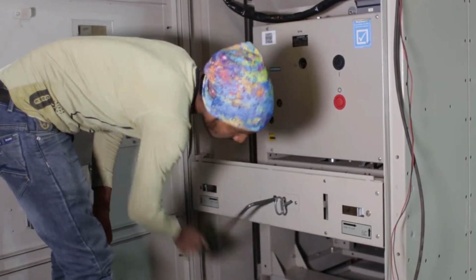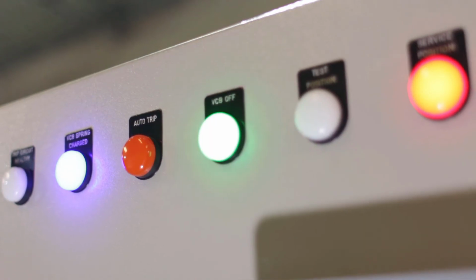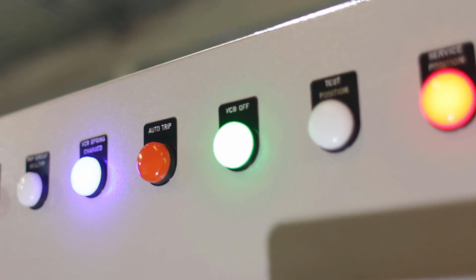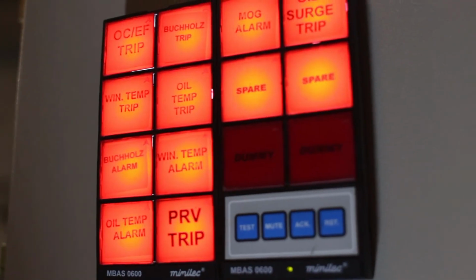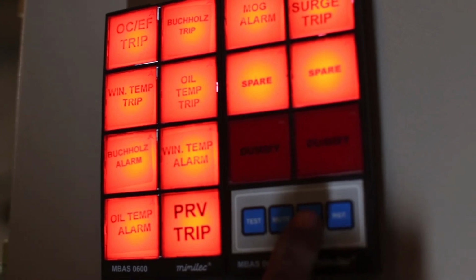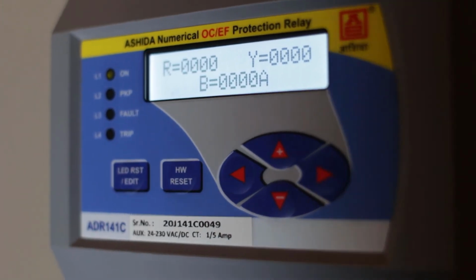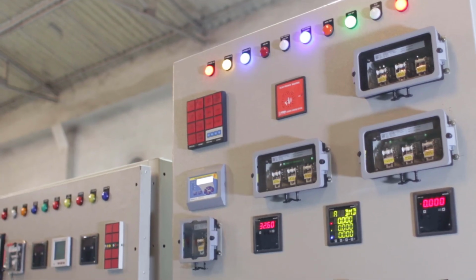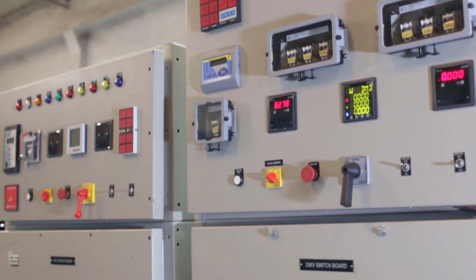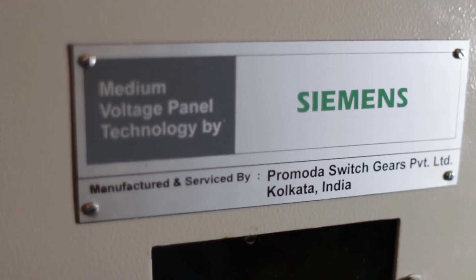Busbar channel is fully segregated from other compartments and is provided with high conductivity electrolytic grade copper or aluminum buses as per customer requirements. Relay chamber consists of protective relays and measuring instrument as specified by customers. All relays are microprocessor based numerical and capable of sensing accurate fault currents.